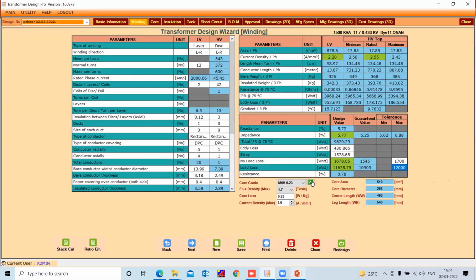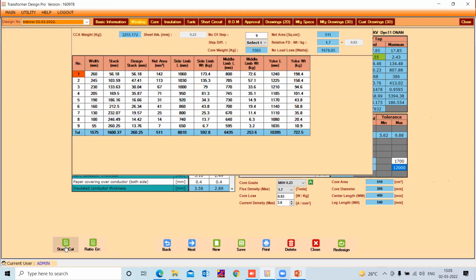Now, friends, I draw your attention to extreme left-hand side bottom corner. You have there the stack calculations. The moment you click on that, you are in a position to see the stack calculations, wherein the information that you get is core coil assembly weight, the sheet thickness, the number of steps, again white background, that means editable. The step difference is editable. The core weight you can see here. The net area you can see here. The relative flux density at which it has designed with the watt per kg, the loss that is also indicated here in the white background. The no load loss is also visible.